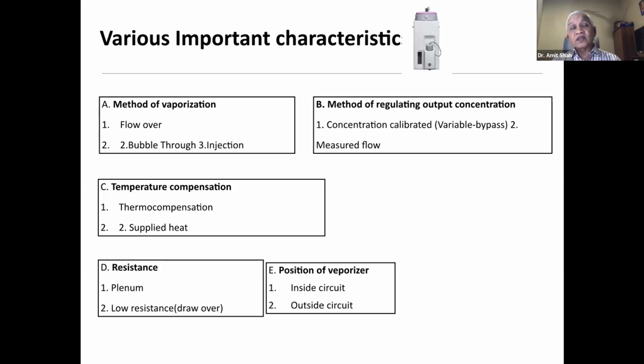Low resistance vaporizers are the older versions of vaporizer, which we can even connect with our ambu bag and give anesthesia, which we used to do when we started our anesthesia practice, or in the field, or in the battlefield and in the war zone, where we do not have modern anesthesia machines. When some anesthetics were given with the help of an ambu bag, they were using low resistance or draw over vaporizers.